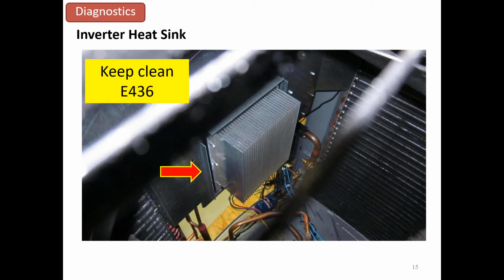Another one that I get very commonly is the 436 code. This is for the inverter heatsink code. So keep this clean. You can spray it off with water. No cleaners, things like that, unless it gets oil stained or something, then we'll use some kind of soap detergent to clean it. Outside of that, it is aluminum. It is sealed through the side back, so you can wash it off. This is how it keeps everything cool. Anytime we're converting voltage from AC to DC, we're generating a fair amount of heat, so we have to keep that heat sink cool.